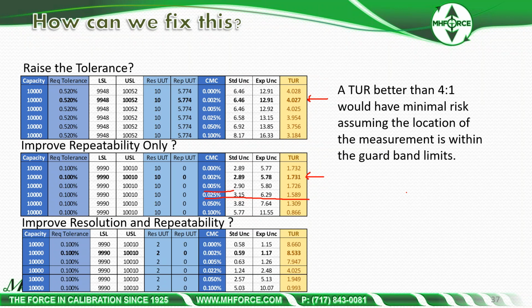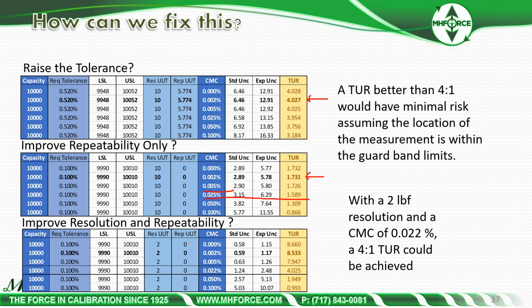We took this scale, we sent it down to JAWS, Jackson Aircraft Weighing Services. They took the guts out of it. They made a lot of modifications to it, and they improved both things, resolution and repeatability. We have a paper on this. It's online, and it's how we derived our CMC uncertainty parameter, because we actually used the scale as a UUT with a resolution of 2 pounds. So with a 2-pound resolution and a CMC of around 0.022%, a 4-to-1 can be achieved. This is important. A lot of people are trying to get this.